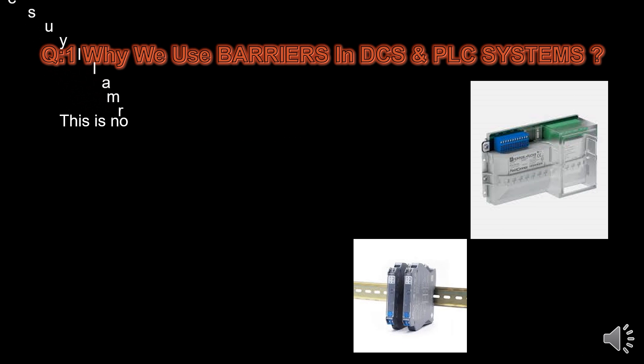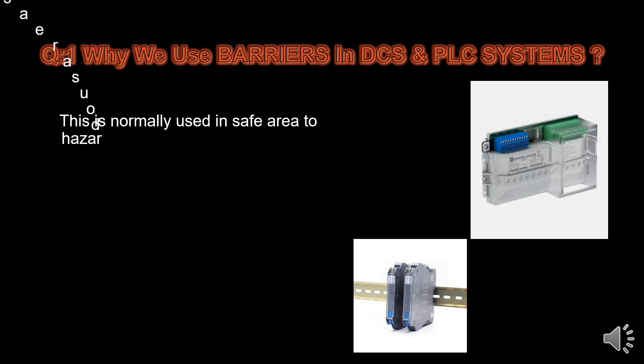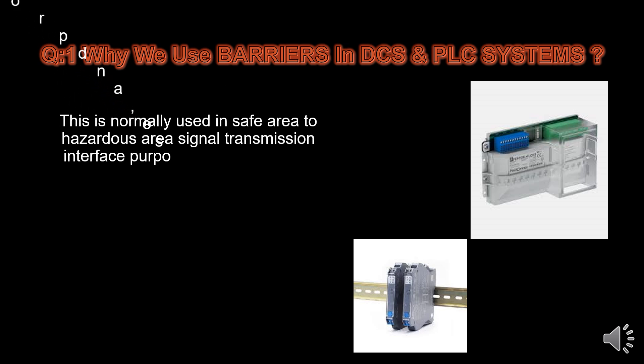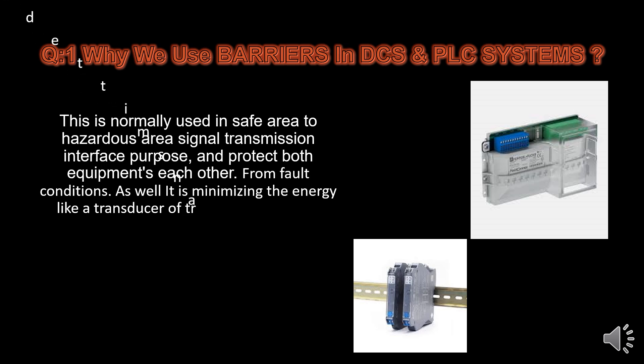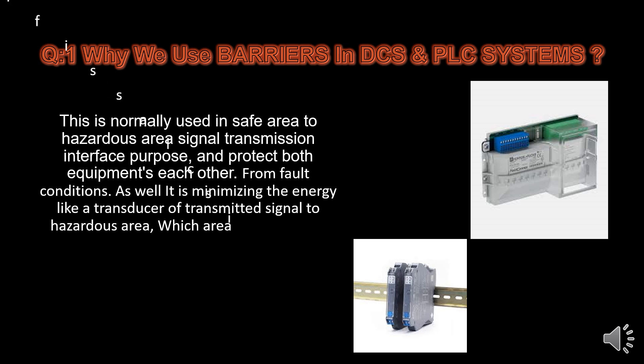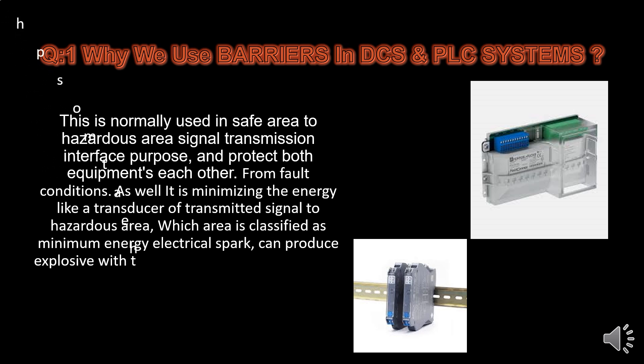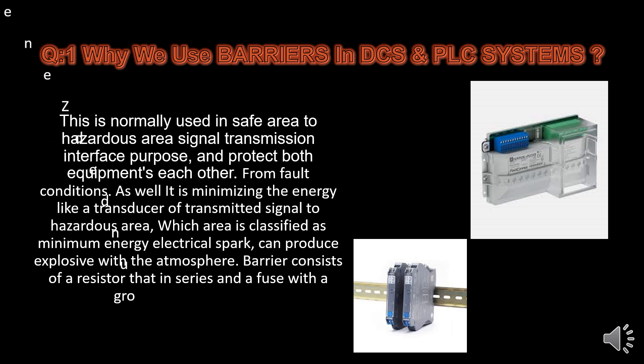Why do we use barriers in DCS and PLC systems? Barriers are normally used as a safe area to hazardous area signal transmission interface, and they protect both equipments from fault conditions. They also minimize the energy of transmitted signals to the hazardous area, which is classified such that minimum energy electrical sparks cannot produce an explosion. The barrier consists of a resistor in series and a fuse with a zener diode to ground.